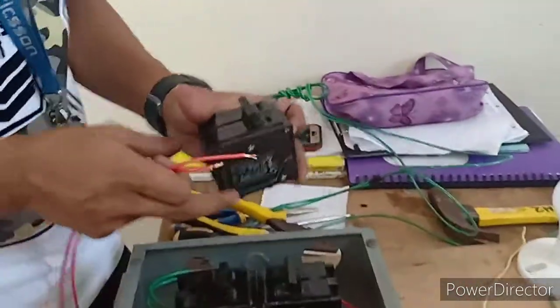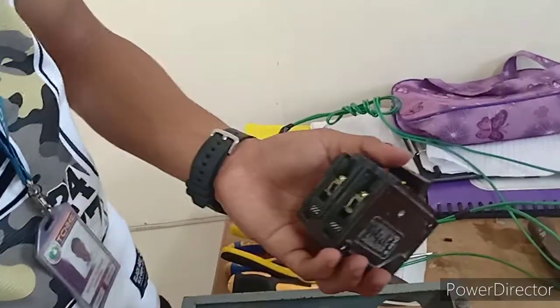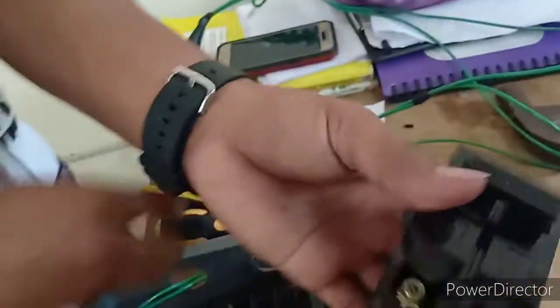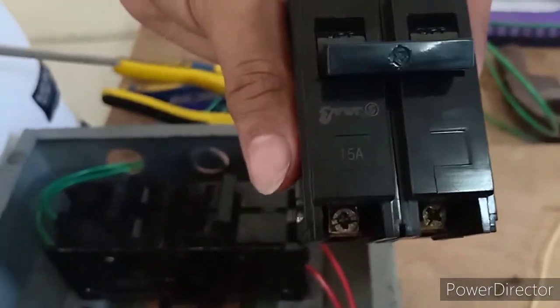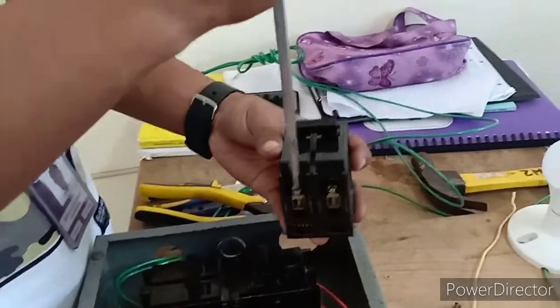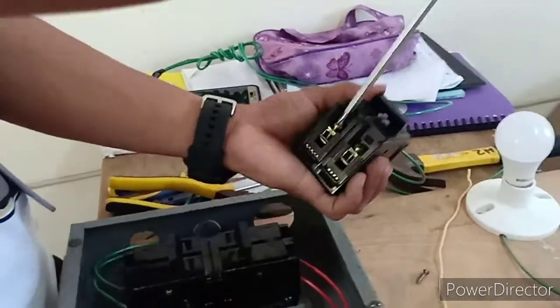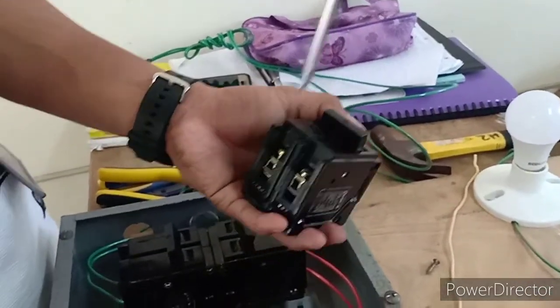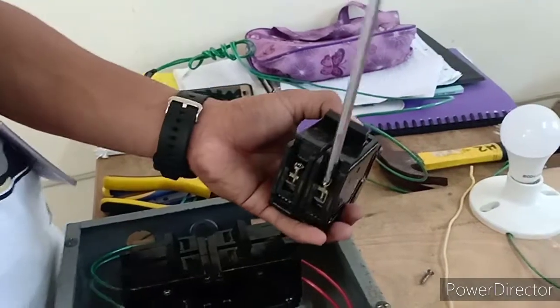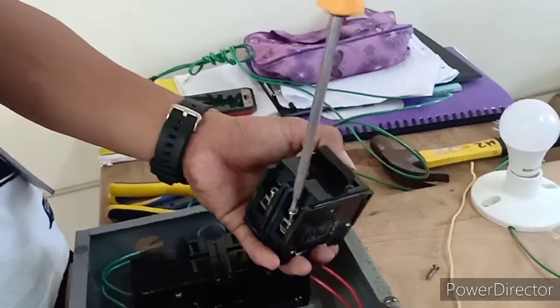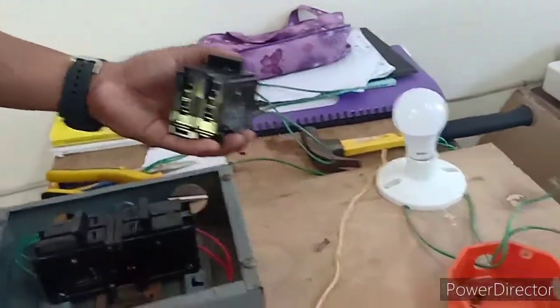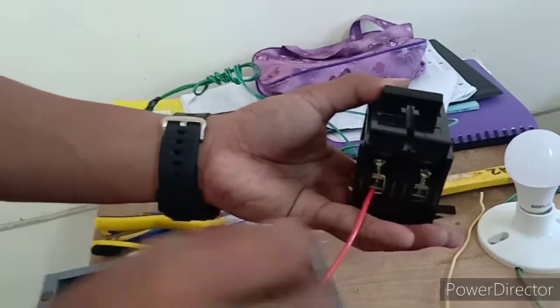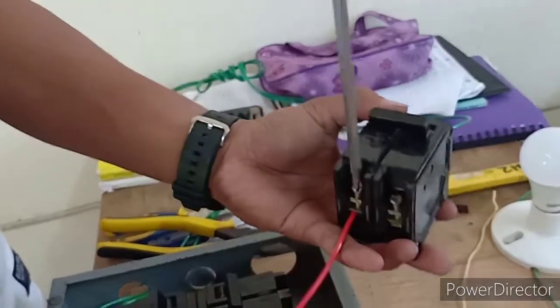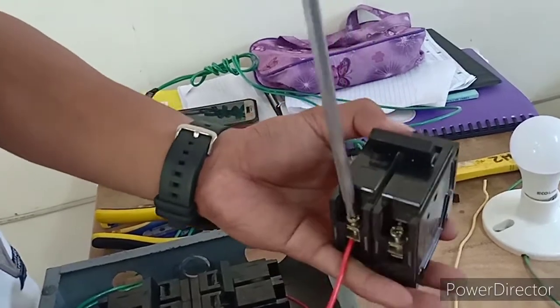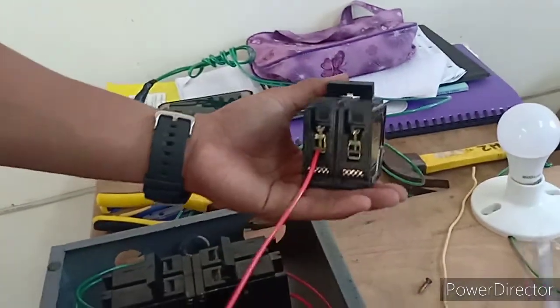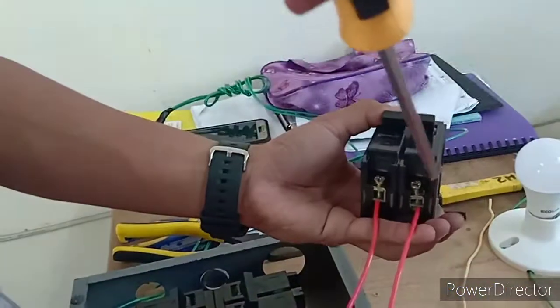Next is you put the circuit breaker 15 amperes for lighting outlet. So that is the 15 ampere. The same procedure, loosen the terminals of the circuit breaker, the line 1 and the line 2 terminals, and then put the line 1, line 2 source of the lighting fixtures. Okay, put the wires on the terminal 1. The next is the terminal 2. Be sure to tighten it.